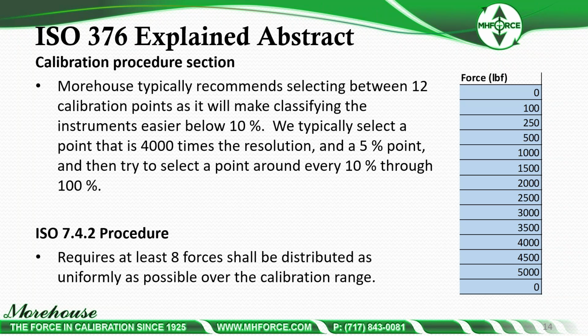So knowing that, our typical suggestion is, we have a 5,000 pound cell here. Our typical selection is 4,000 times the resolution as our first point if we know the customer wants a class 00, and a 5% point. And then we try to select a point around every 10% through the 100% of the range.